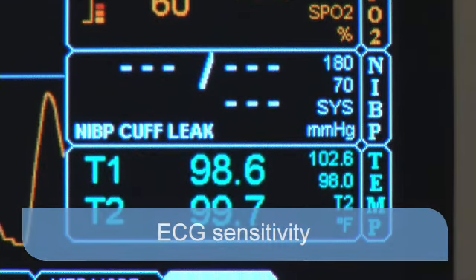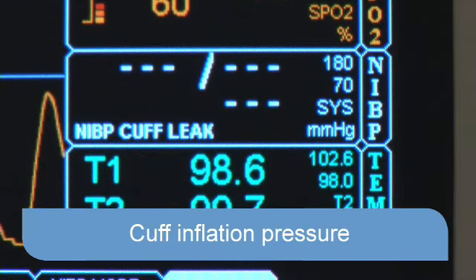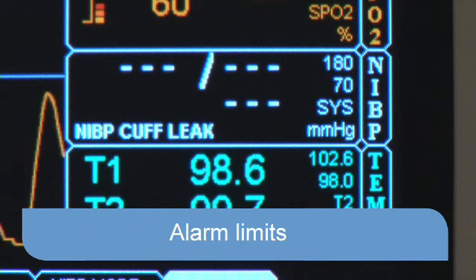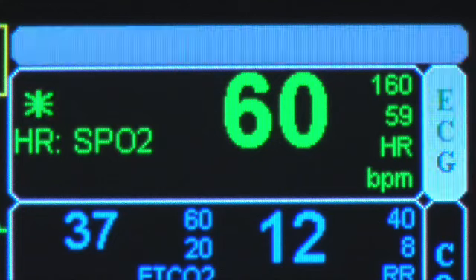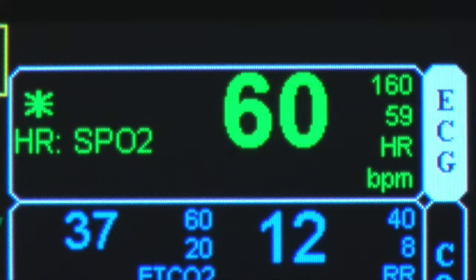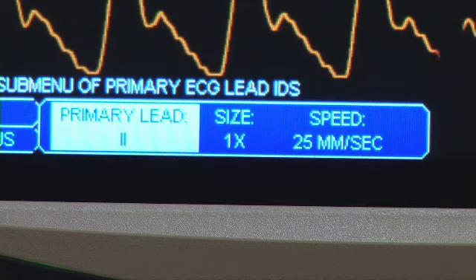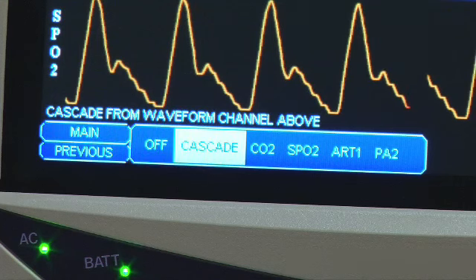The Monitor features three monitoring modes that adjust ECG sensitivity, cuff inflation pressure, and alarm limits, allowing it to be tailored to the physical requirements of the patient. The ECG parameter has both three and five lead monitoring capabilities with options to select lead-specific viewing, amplification of lead signal display, and ECG cascading.